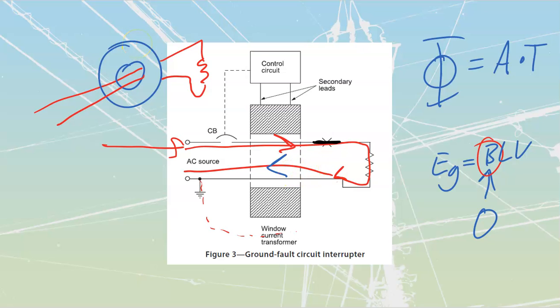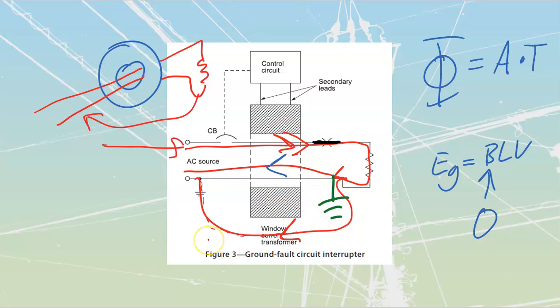As soon as we get that ground fault happening on the correct line over here, we are going to divert some of that current. It is going to go around, like what we're showing over here, back to my neutral, which is going to be grounded down. And when it does that, we have unequal amounts of flux, which means that we do have a certain amount of net flux. There's more flux going through in this direction than what I have going through in the opposite direction, because someone's bypassing. Which means that if there is flux, and if I've got enough turns, there'll be loads of turns on these, then I am going to generate a small value of voltage, and that's going to kick my circuit breaker.